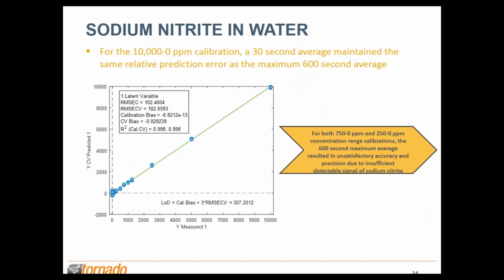And similar to the propylene glycol, for the 10,000 to 0 range, the 30-second average maintained the same relative predictive performance as the maximized 600-second average spectrum. Again, it's a simpler model because we have a strong single peak. It was a single factor model with an average predictive error, the RMSECV, of 103 ppm. And the calculated LoD was determined to be 307 ppm. And again, with a smaller Raman cross-section and a more dilute sample, any further reduction in the calibration range, 750 and below, did not leave enough spectral variation in the data to generate a satisfactory multivariate PLS calibration model.